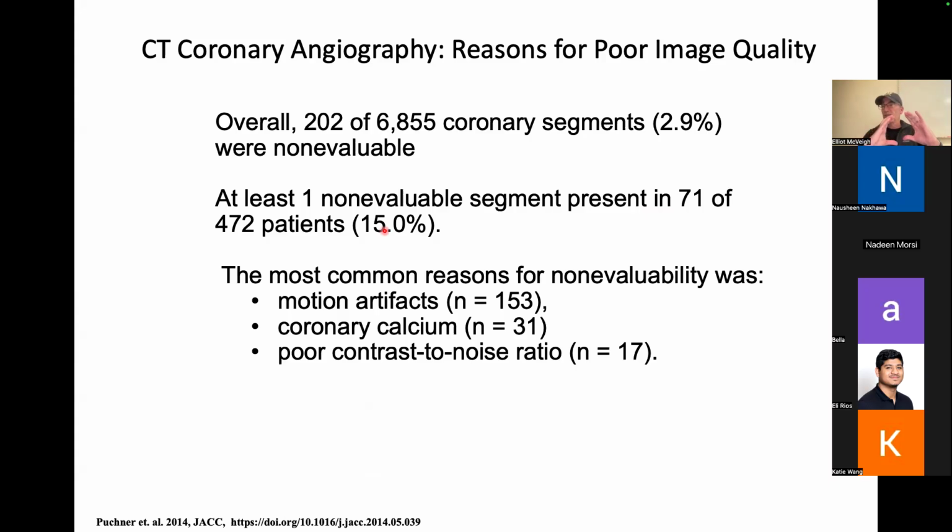If you just put a phantom in the scanner on its own without anything around it, and you take pictures of it, they will look spectacular. They look absolutely beautiful. And you might ask, well, why do these look so good compared to my clinical scans? Clinical scans, the thing you're looking at is surrounded by a large human. So you need to essentially simulate that. And so we have these rings that we put around our phantoms that reduce the number of photons that actually get to the phantom, right?